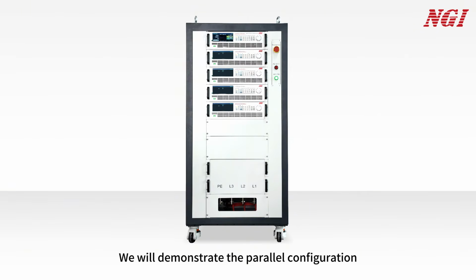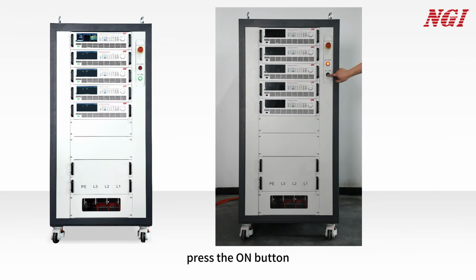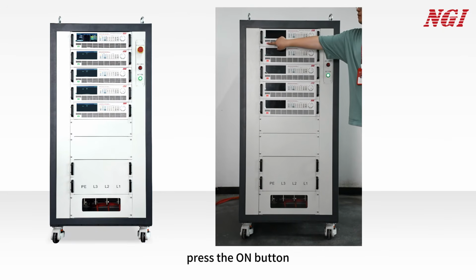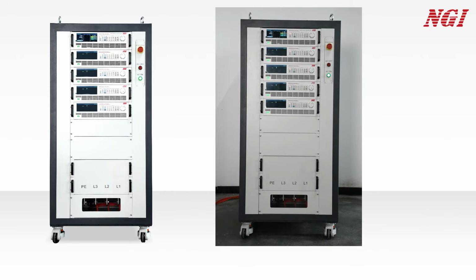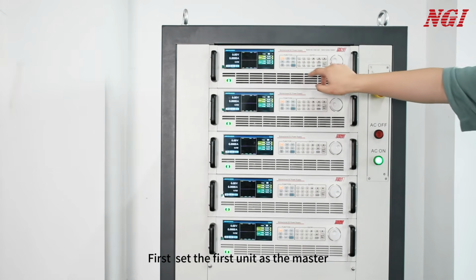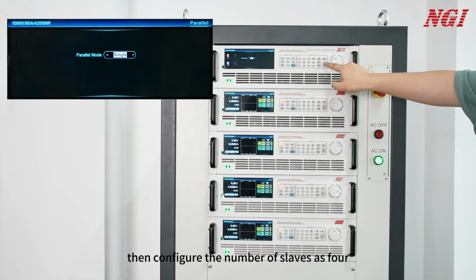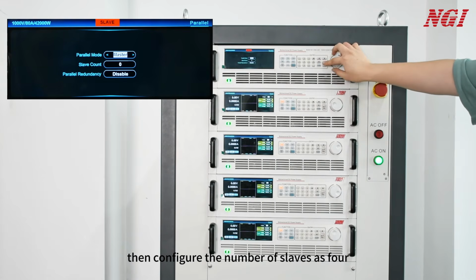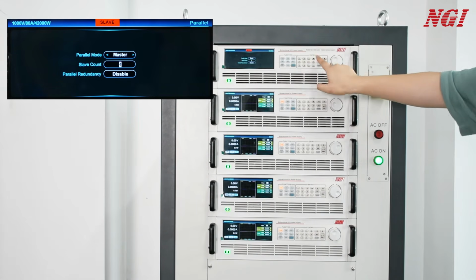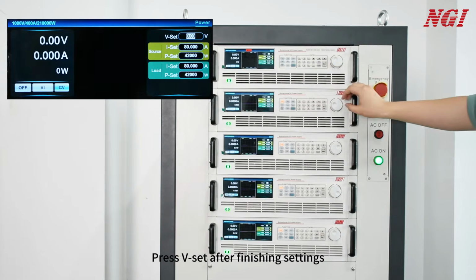We will demonstrate the parallel configuration using 5 units as an example. After completing the electrical and optical fiber connections, press the on button. First, set the first unit as the master, then configure the number of slaves as 4. Press V-set after finishing settings.